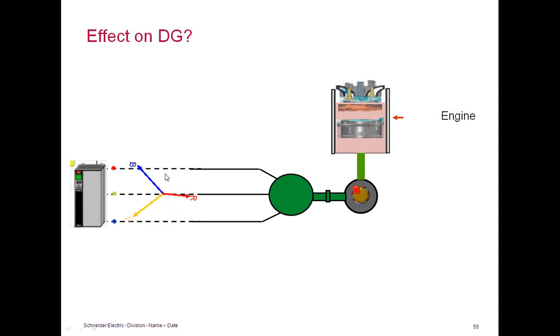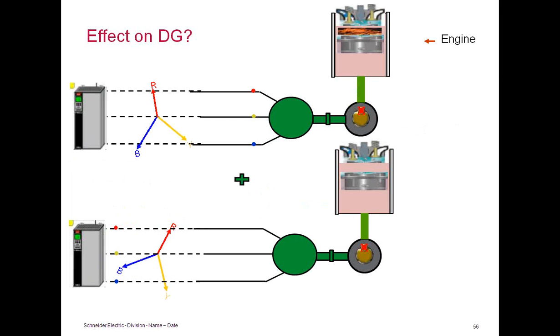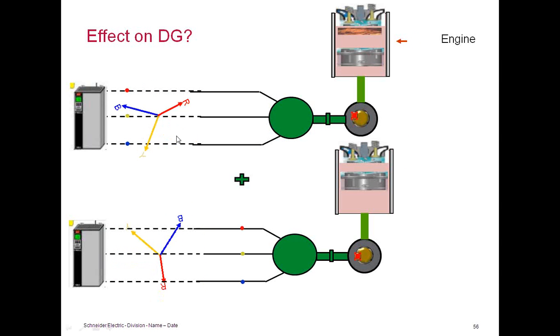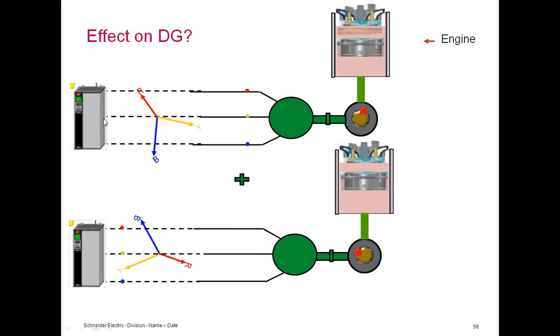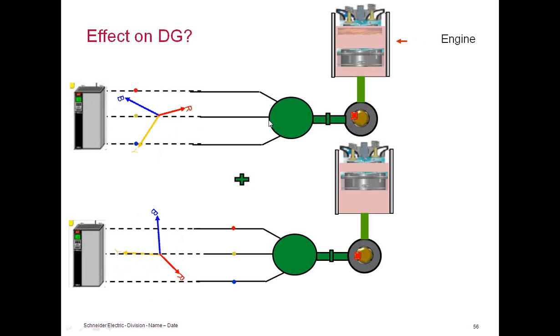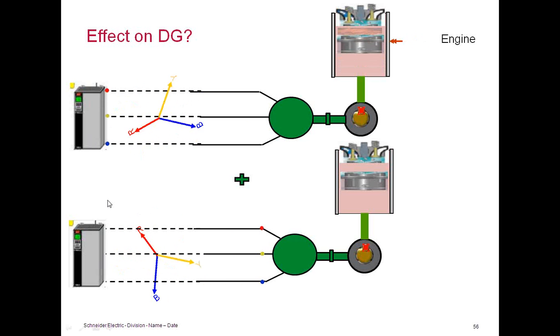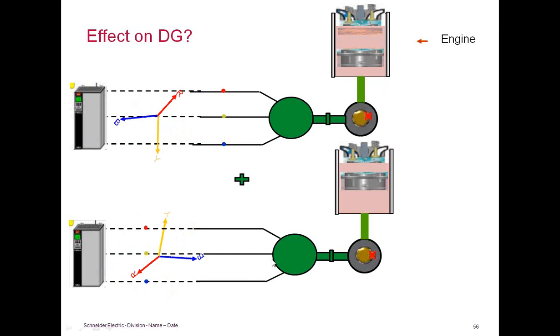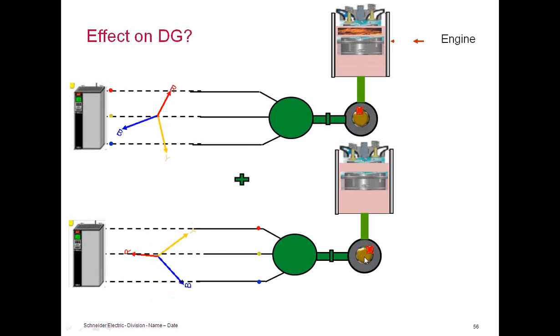the top animation. We have the load of a variable speed drive or maybe a UPS. The normal power, 50 hertz power, is going from the alternator towards the drive. If the drive is a 6-pulse converter, it will pump fifth harmonic current, negative sequence harmonic current, back into the generator winding, and that in turn is transferred to the shaft, and we are going to have a negative torque on the shaft itself.